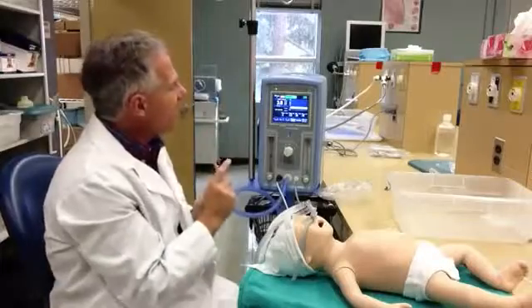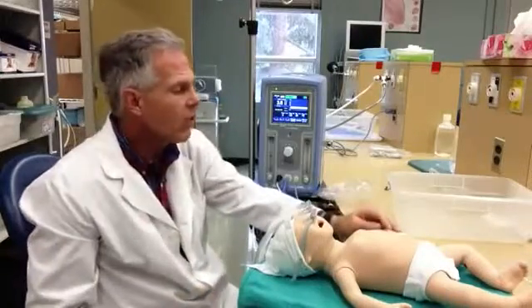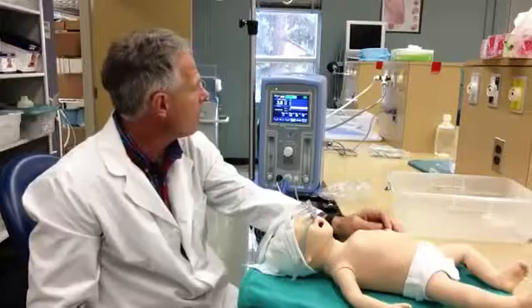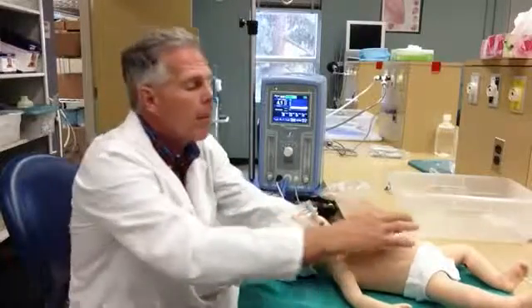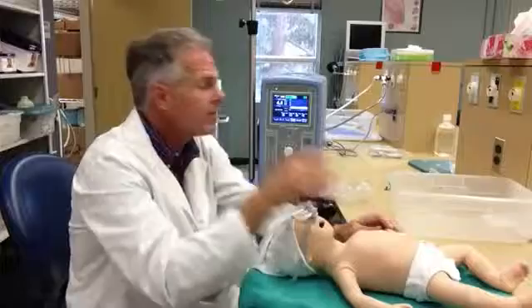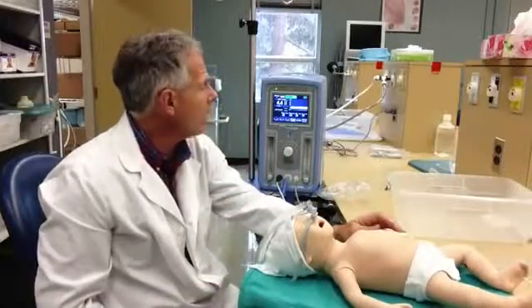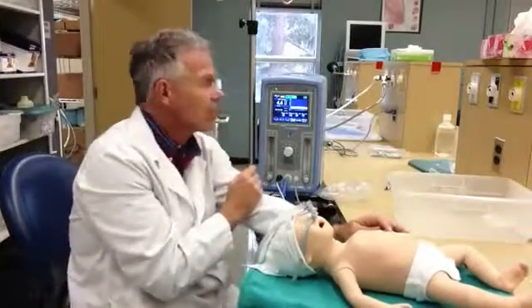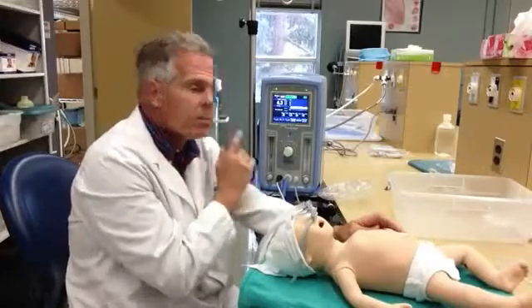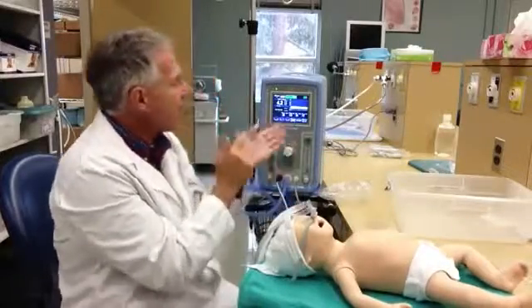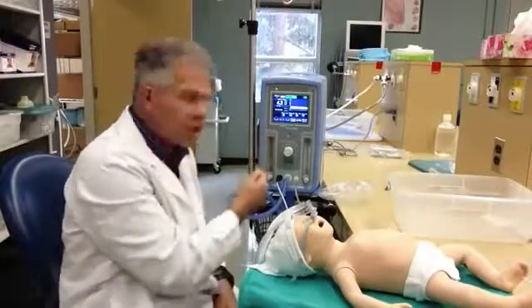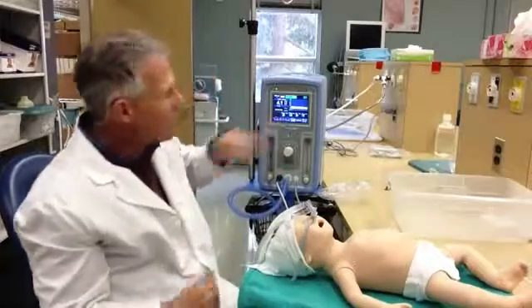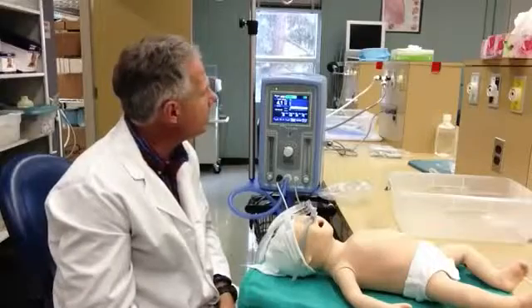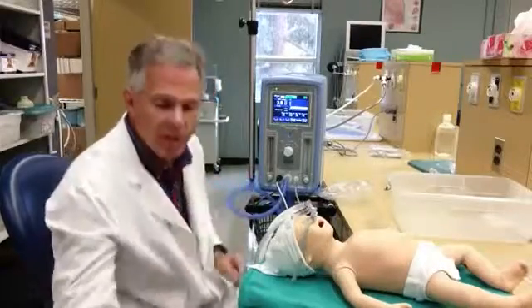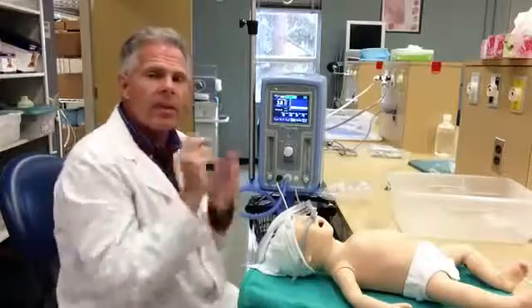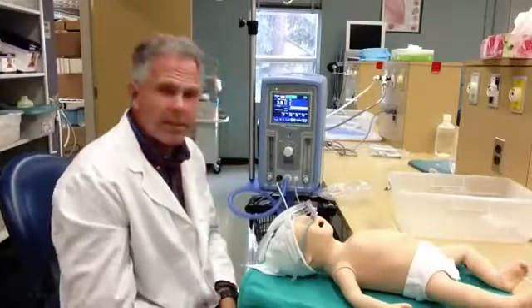Confirm we want biphasic now. It shows me what I've got here. Every time the patient breathes in and creates a little bit of pressure against that sensor, this ventilator will pick that up as a sensitized breath. You can actually watch that on the screen and see when it's picking up. If the patient goes apneic for more than 15 seconds, it'll just kick in and give your backup rate, whatever you've got established there. Now, the alarms on this ventilator are set automatically. You don't have to do anything to set up the alarms.